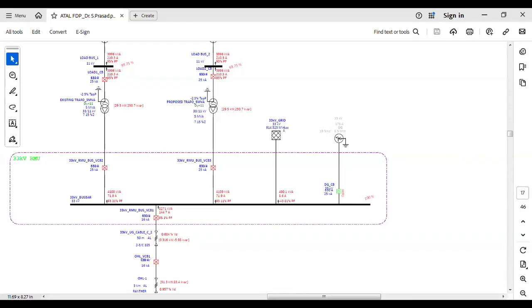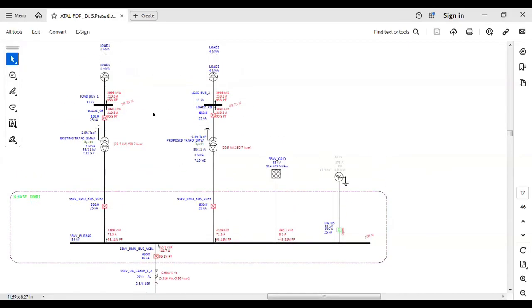It has to be specified by the utility, either in terms of ampere rating, X by R ratio, or MVA. You will get that information from the grid, because you are going to inject the PV plant at this grid bus. So this is called the grid bus, and these are the two existing ones.